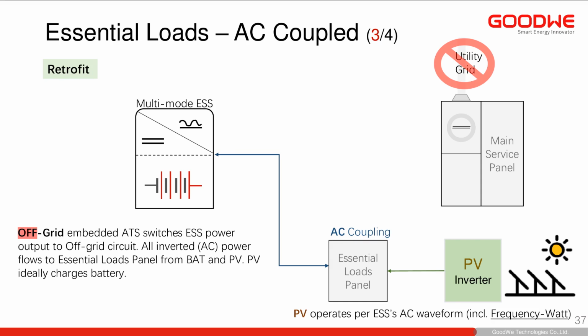Now, when we have this kind of AC coupling going on, it's good to note, and you would like this to exist, that frequency watt functionality exists in the existing PV inverter. It may be an old inverter and not have it, even a slightly newer one, but you should still test. And what we mean by this is if the PV inverter is overproducing in the sense that the essential loads don't need more power and the battery is fully charged, the way for an ESS to communicate to the PV inverter without additional wiring is to change the frequency of the AC waveform to tell the inverter to ramp down. That's our frequency watt functionality, and you want to make sure that exists in this type of setup.